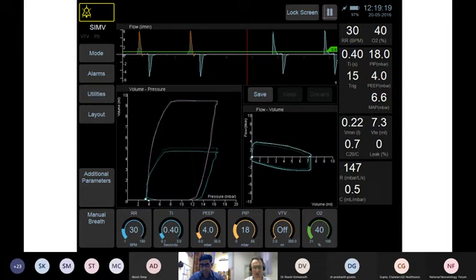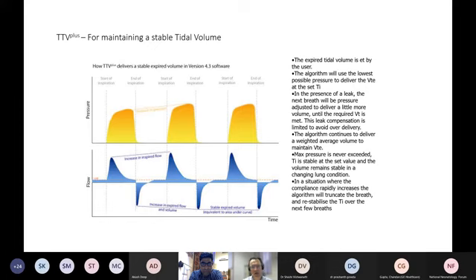with the ventilator. You see also here the volume pressure curve. This is derived from the flow sensor data. The volume pressure curve can give us an idea of how the lungs are extending during ventilation and whether we're putting too much volume in over a period of time. The same with the flow. So the flow sensor, that one small accessory, is giving us access to a whole bunch of new things in a ventilator that weren't there previously. So if I kick on a little bit, one of those things is the ability to start maintaining a stable tidal volume.